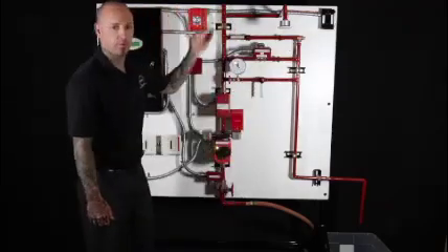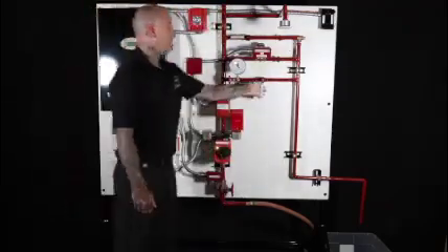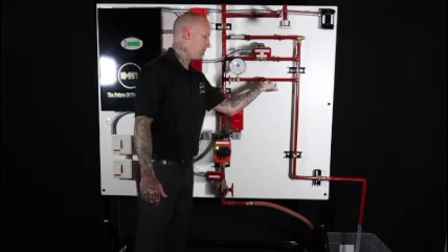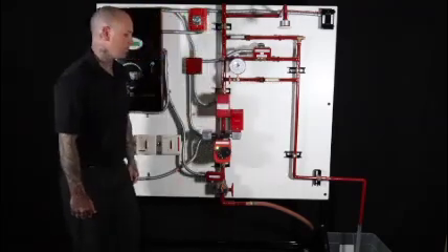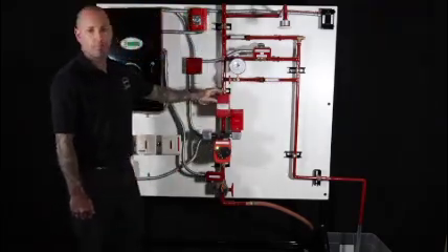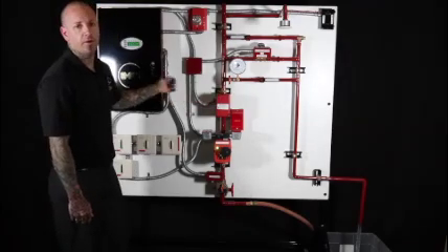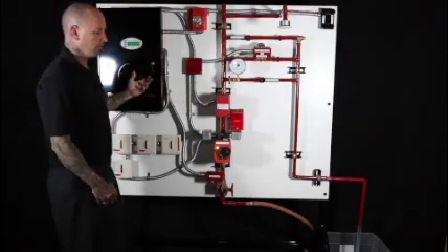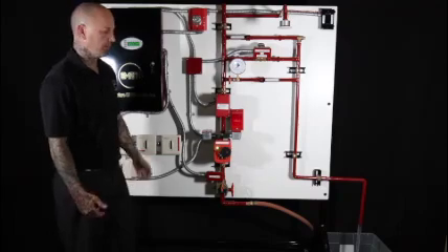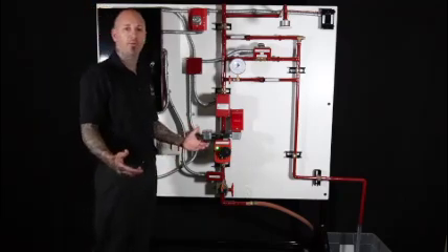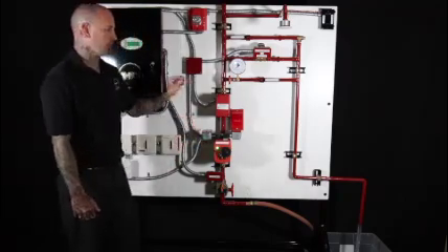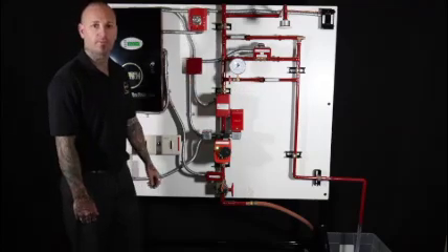Activate the switch. You have a sprinkler head flowing water. Simulate the water flowing. Soon after, the flow switch device will send an alarm signal calling the fire department. This is normal operation. I now have to shut the system off manually.